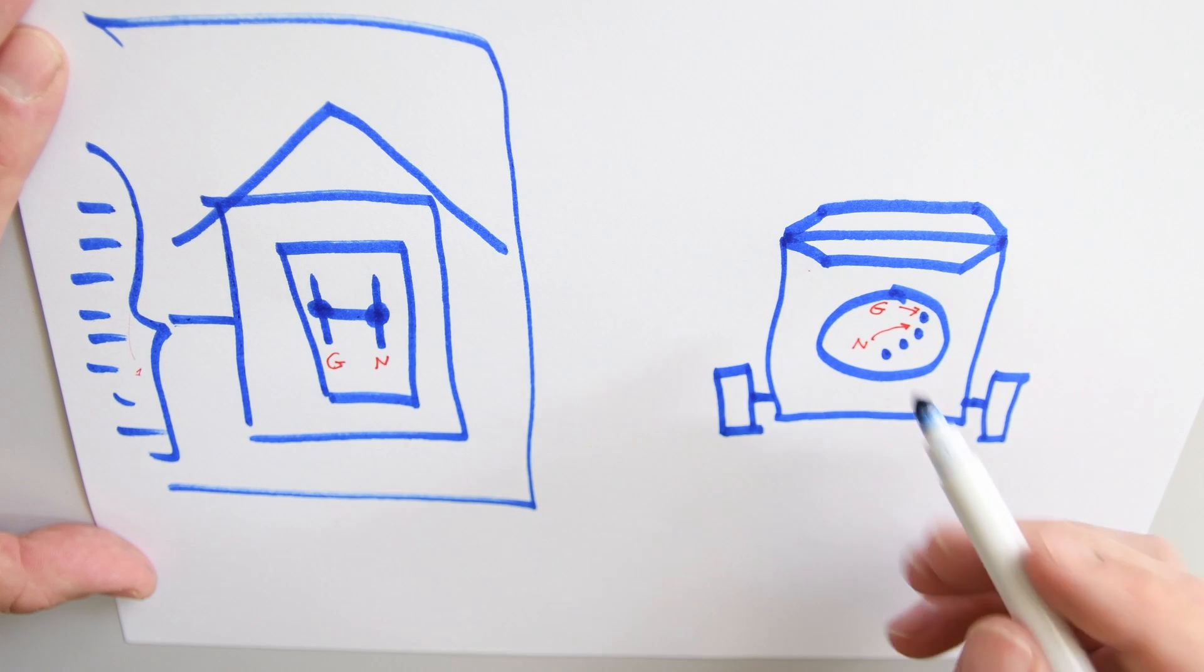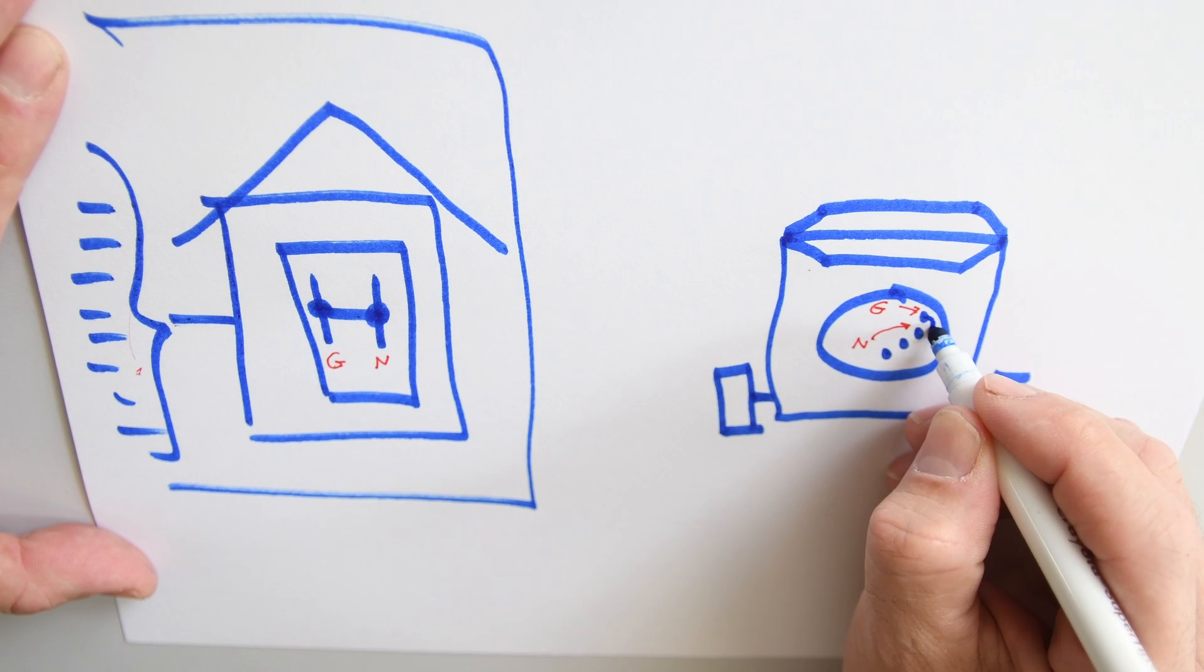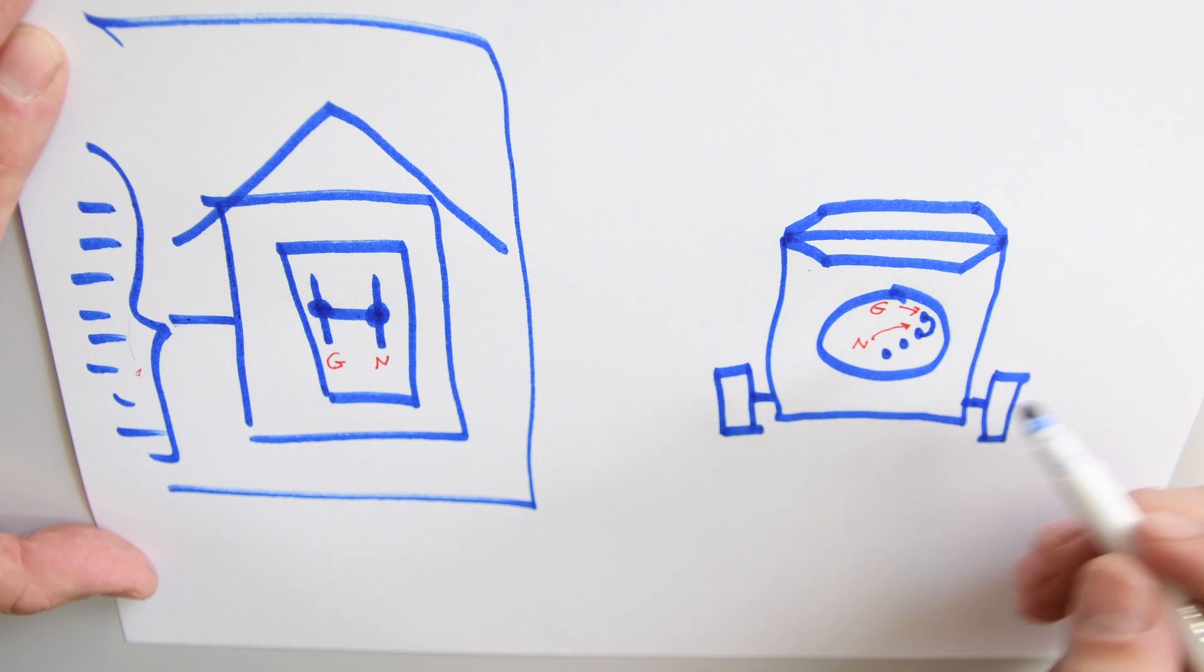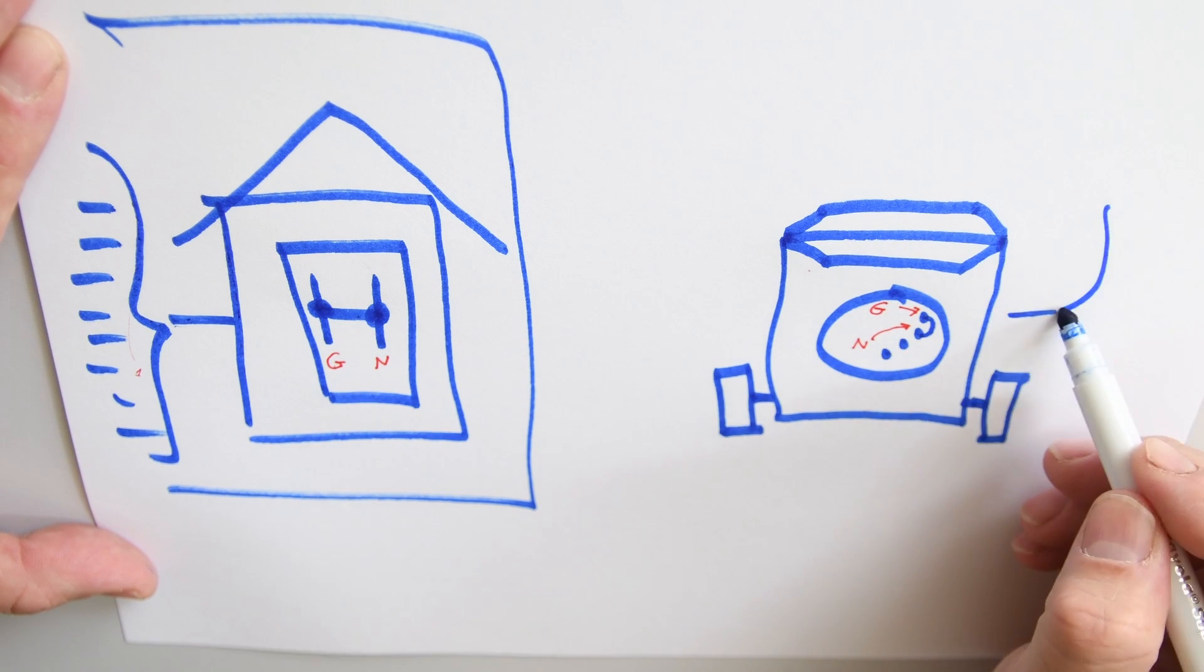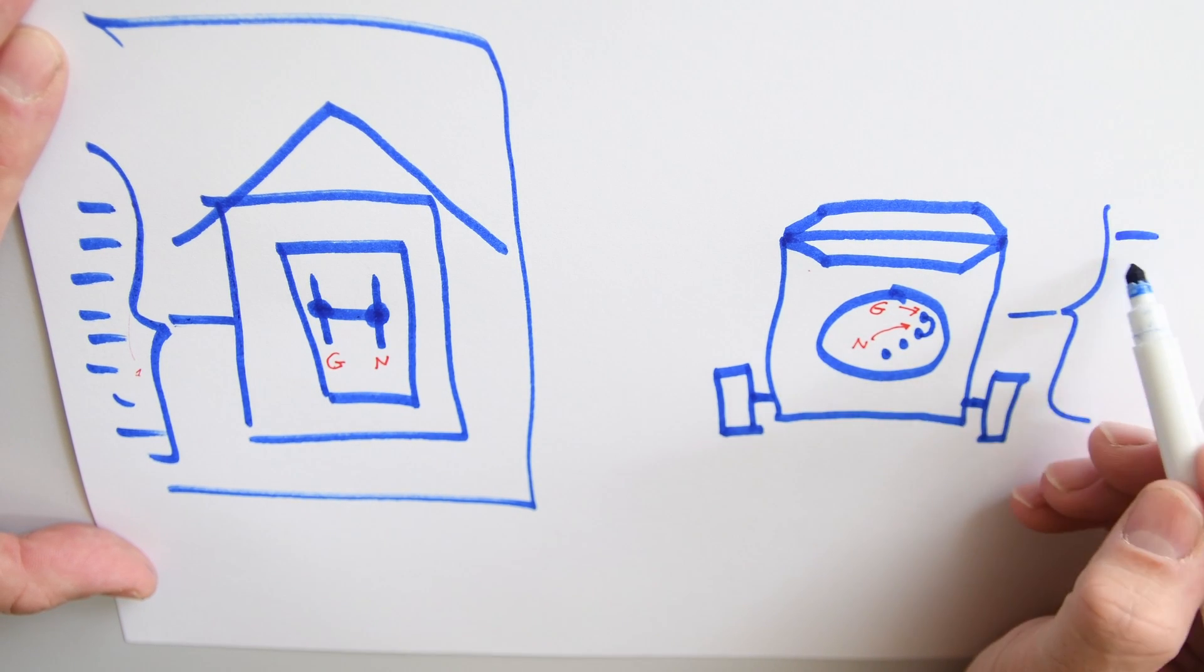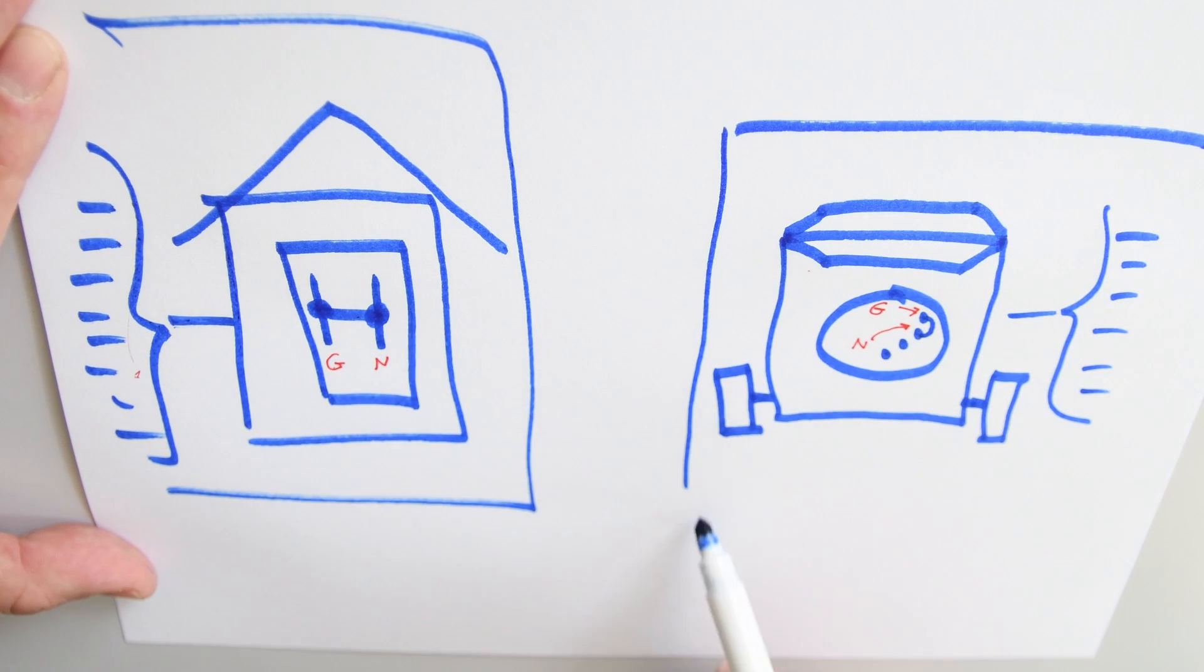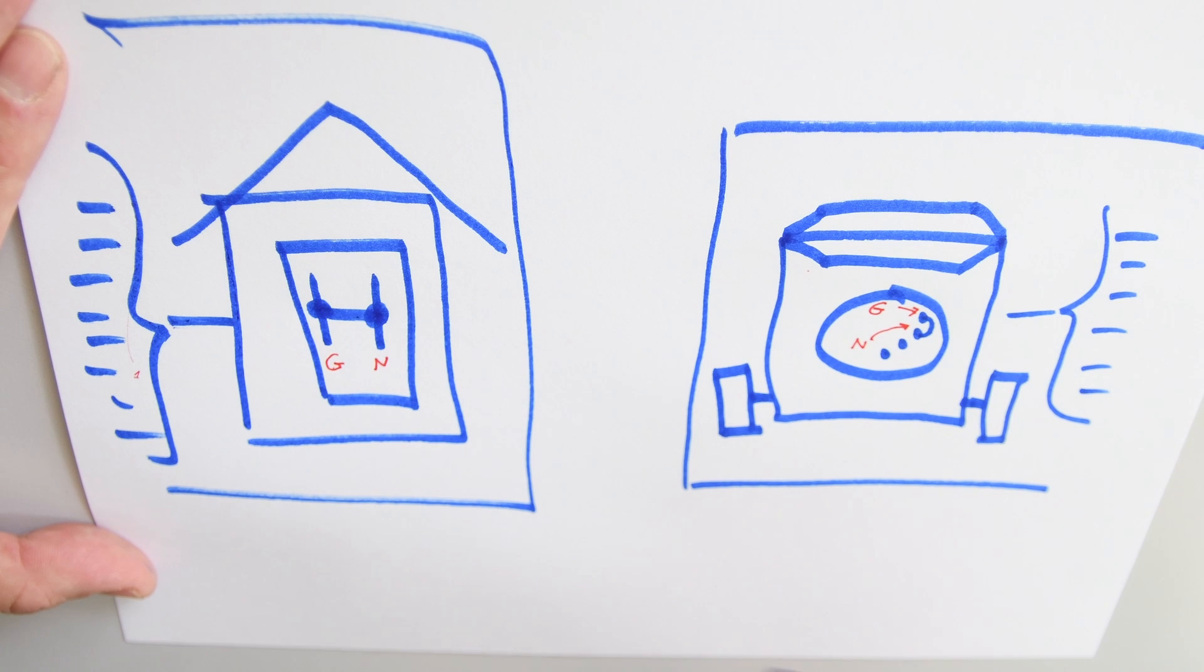So you can see when you open this cover that the ground is reached to the neutral. That means that anything that we connect to the generator, any power tools, whatever, in this system there's going to be only one place where the ground is bonded to the neutral. It's not going to happen on any of these tools. It's going to happen only on the generator. So this is compliant to the National Electrical Code.